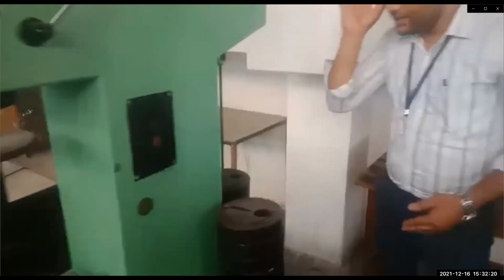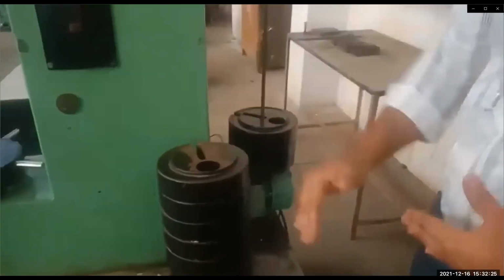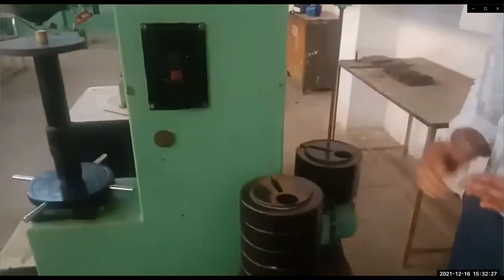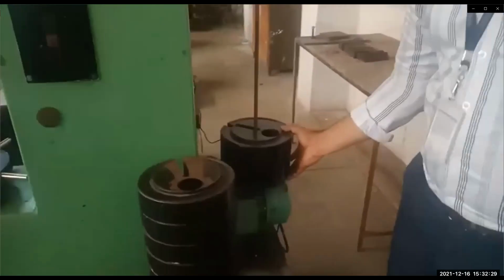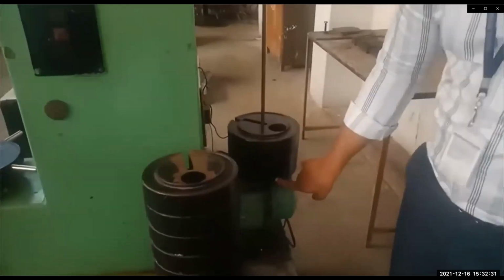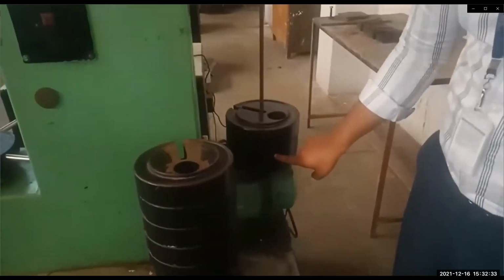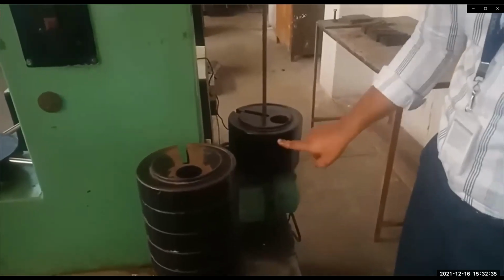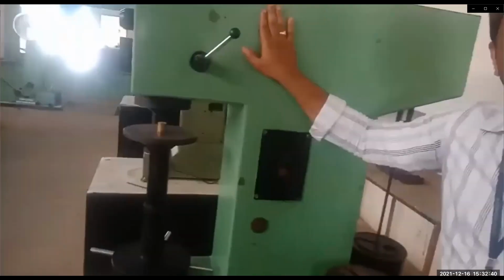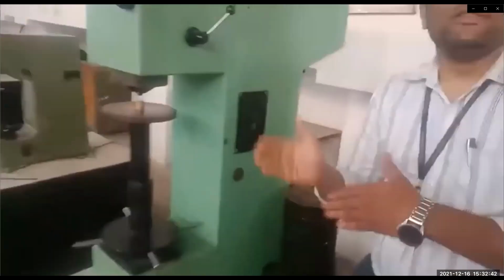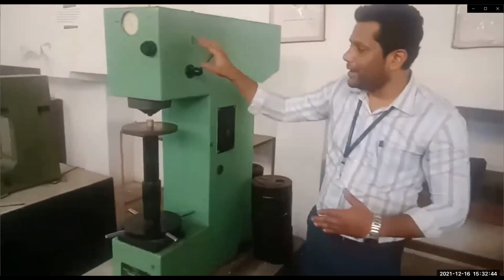Before I conduct the test, I will choose the load. What is the load we are applying onto the ferrous as well as non-ferrous? For the brass we are applying a load of 1000 kg. That means the pan is 250, another one is 500, that is 250, once again 250. Total is 750, and the inbuilt contains a weight of 250. Totally the effective 1000 kg is going to be acting onto the indenter.